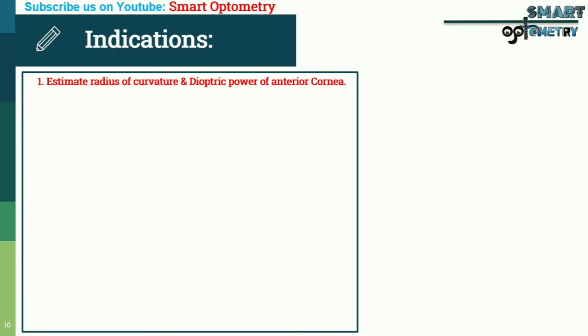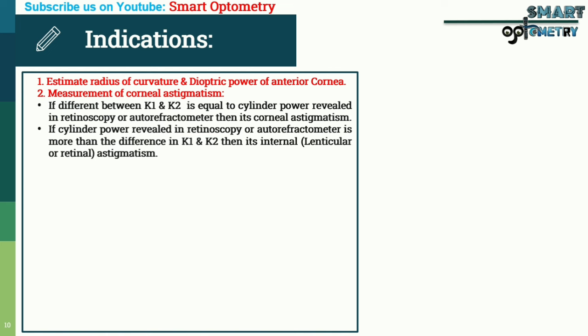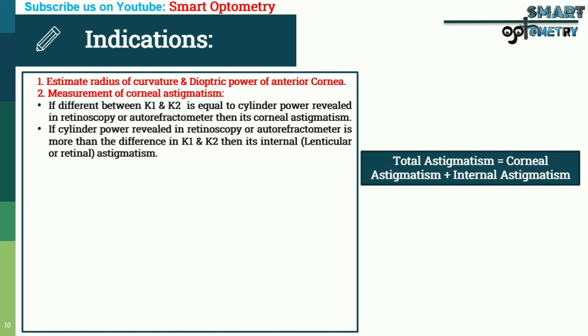Indications of keratometer: (1) Estimate radius of curvature and dioptric power of anterior cornea. (2) Measurement of corneal astigmatism — if the difference between K1 and K2 equals the cylinder power in retinoscopy or autorefractometer, it is corneal astigmatism; if the cylinder power is more than the difference between K1 and K2, it is internal (lenticular or retinal) astigmatism. Total astigmatism = corneal astigmatism + internal astigmatism.